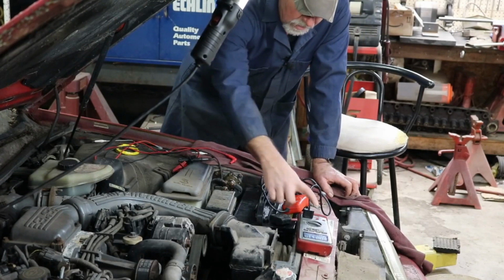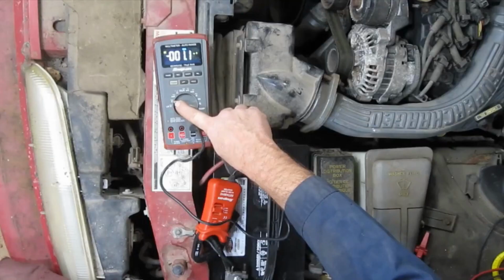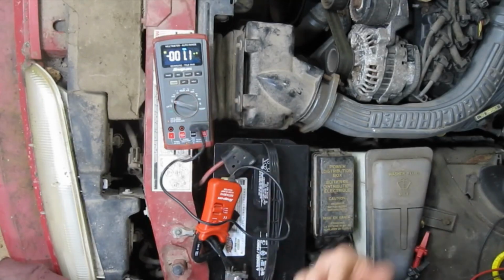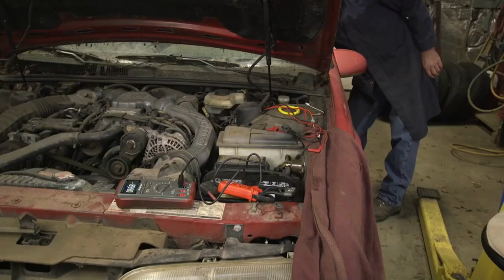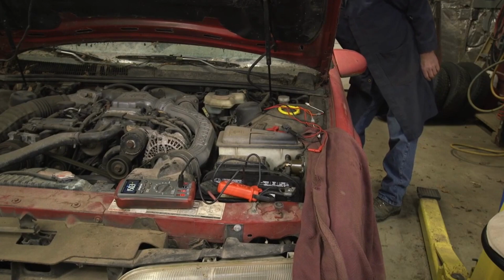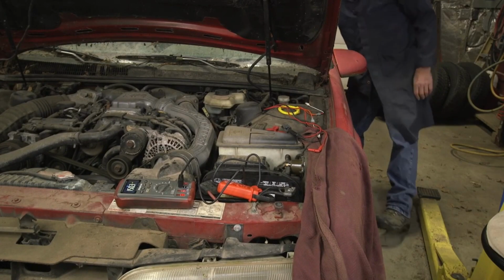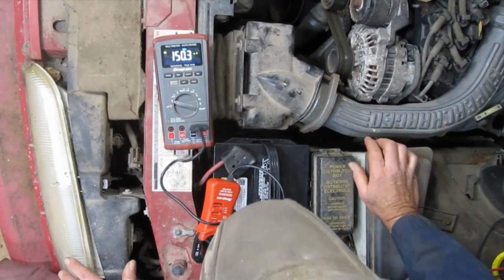I went to the standard volts instead of the millivolts because I know it's going to be a lot of current. We're set for max. Let's go ahead and see what we have for inrush current. Okay, 150 amps.